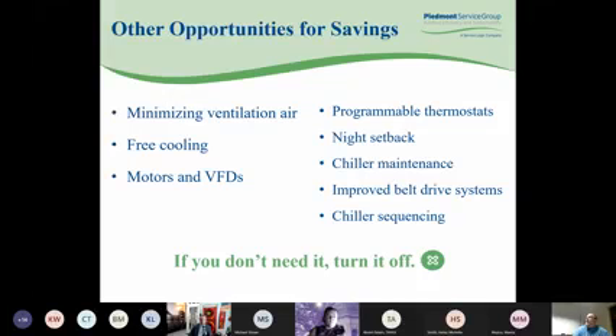In heating and cooling load calculations, the introduction of outside air is usually a large thermal load. Controlling the outdoor air to the minimum required for a safe working environment will save energy. ASHRAE 62.1 is our ventilation and acceptable indoor air quality guide. The ACCA Manual N is used for HVAC load calculations, with Table 14 giving ventilation requirements. Good ventilation means having enough ventilation, but not too much. Too much ventilation doesn't help at all and just makes buildings drafty.